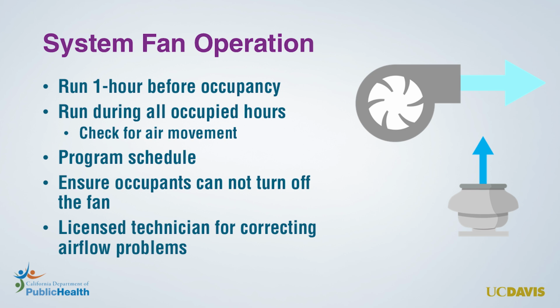Document any supply air or return air vents that appear to lack air movement in an inspection report for follow-up by a licensed technician. A licensed technician can configure control systems correctly and fix any problems with airflow distribution. Next, you'll want to inspect all of your outdoor air intakes.